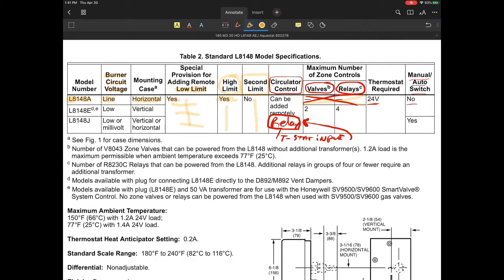All right, so let's take a look at the E model. The E model is one of the very common Aquastat relays. This particular one has a low voltage burner circuit, so that would usually go to a 24 volt input on an ignition module, if you have an electronic ignition system. The mounting case is obviously vertical, and I don't worry too much about those things. All the other things I don't need to go through anymore. But here's the kicker.